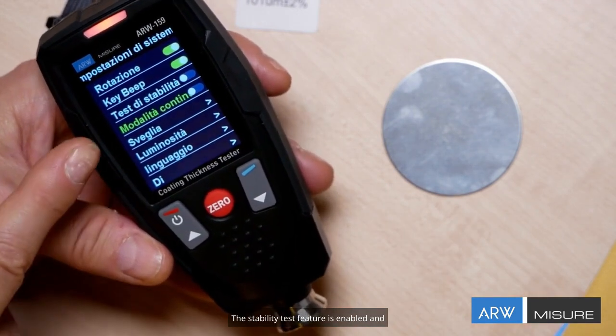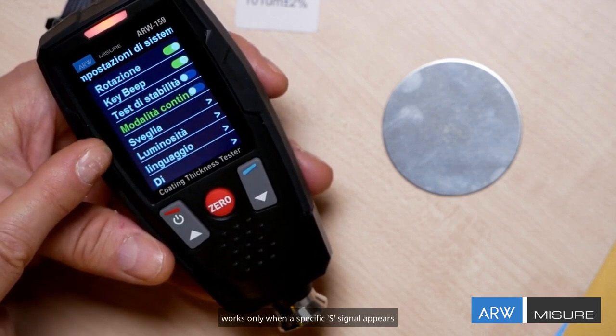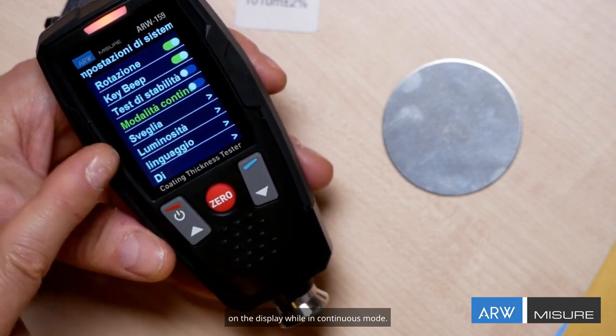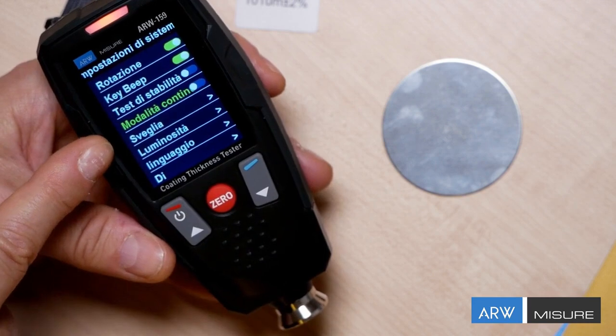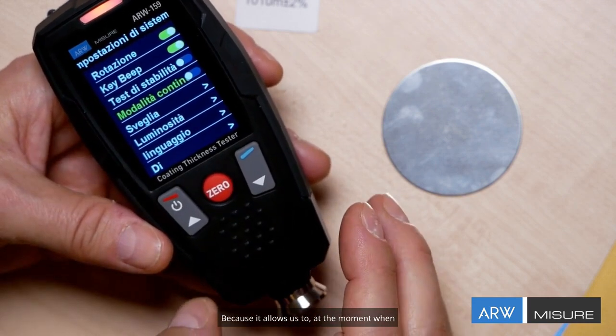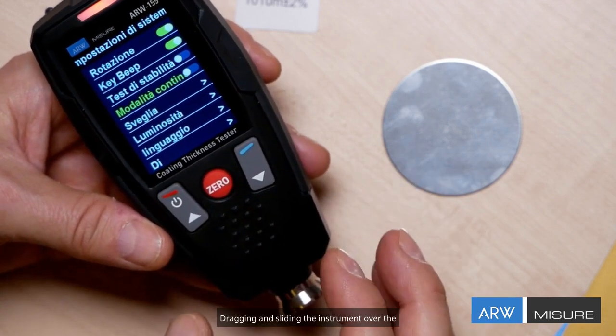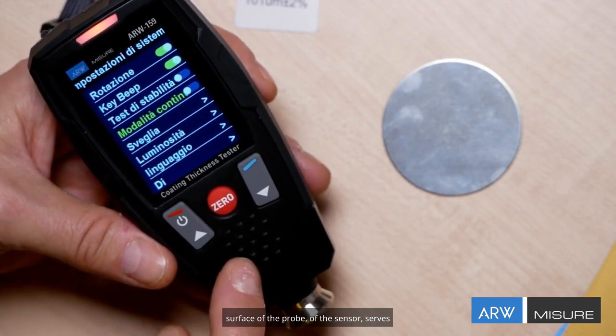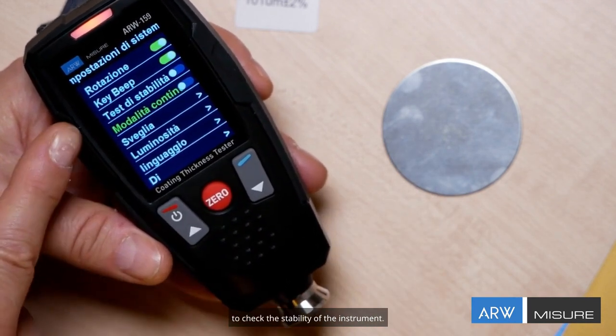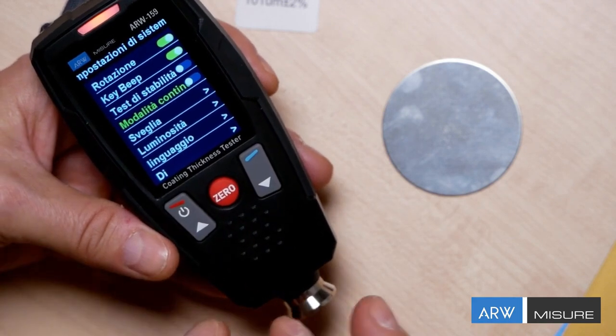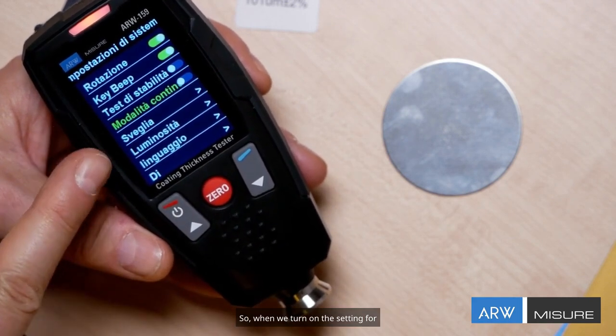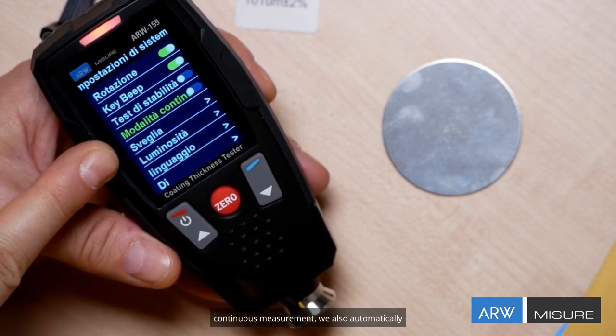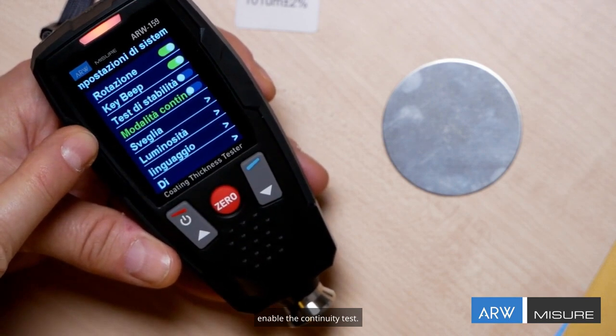The stability test feature is enabled and works only when a specific S signal appears on the display while in continuous mode, because it allows us, at the moment when we perform dragging and sliding the instrument over the surface, to check the stability of the instrument with the probe of the sensor. So, when we turn on the setting for continuous measurement, we also automatically enable the continuity test.